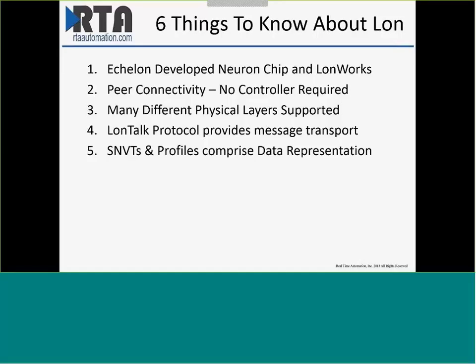Fifth is data representation. In LonWorks, data is represented using SNIVETs — Standard Network Variable Types. LonWorks defines a number of SNIVETs, each being a specific data type. You can only connect devices using the same SNIVET type. For example, a light switch has a binary output SNIVET and a light expects a binary input SNIVET — they're the same type, so they can talk. Profiles are what result when you combine a standard set of SNIVETs to define a standard device type.